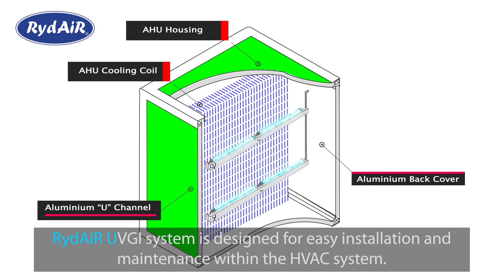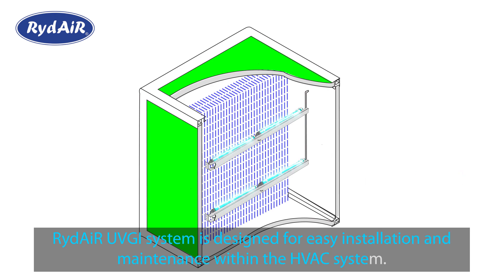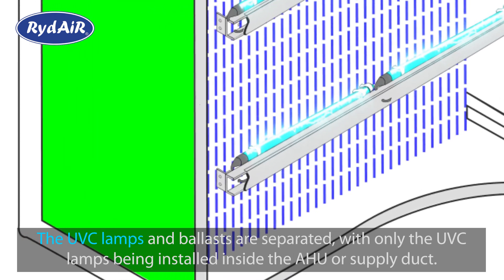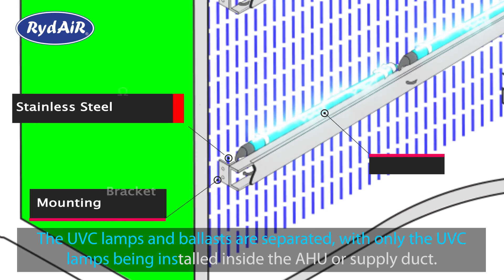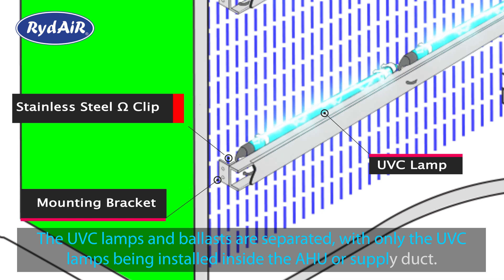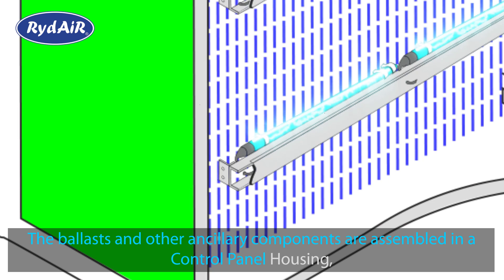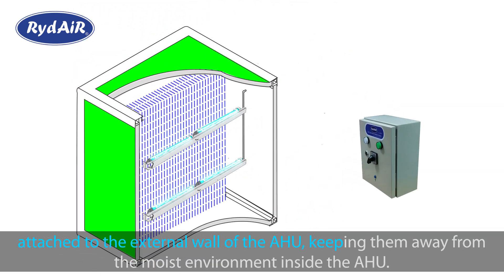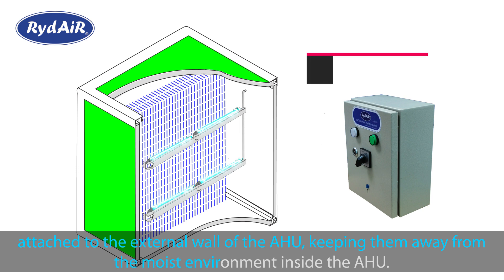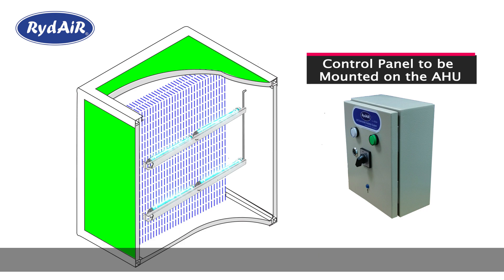The RydAiR UVGI system is designed for easy installation and maintenance within the HVAC system. The UVC lamps and ballasts are separated, with only the UVC lamps being installed inside the AHU or supply duct. The ballasts and other ancillary components are assembled in a control panel housing attached to the external wall of the AHU, keeping them away from the moist environment inside the AHU. This makes it very convenient for servicing, maintenance, and troubleshooting.